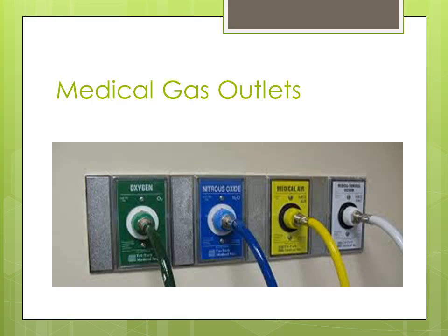Here's a classic oxygen outlet, or medical gas outlets, pretty typical. There are different styles of outlets. One thing to keep in mind about outlets, and this is something I ran into with one of my facilities, is as we had different revisions of buildings added onto each other, we lost standardization of outlets, and we ended up with several styles of outlets. Some outlets require different ways to connect them.